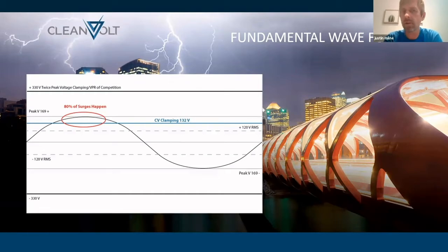So if the manufacturers of our equipment and electronics are suggesting a 10% tolerance of RMS, and NEMA is stating that 80% of surges are found within the fundamental waveform, it's important to have a surge protector that has the levels and the ability to address those energy surges that are common in your system, and keep the connected tolerance levels suggested by the manufacturers as close as possible to those levels, if that makes sense. You can find that on spec sheets for these surge devices, and feel free to take a look.